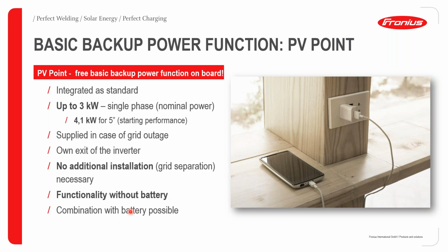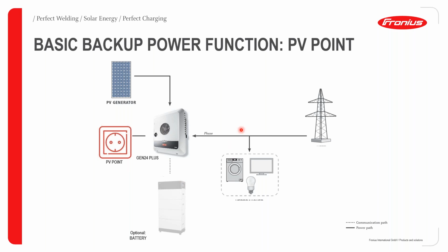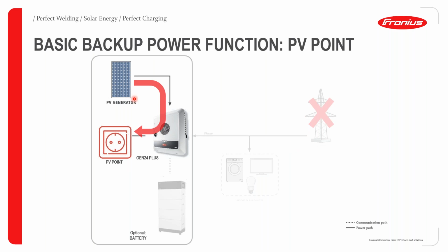So the combination is also possible with a battery system. If you have a battery system integrated, this is how a normal setup would look. You have a Gen 24 inverter connected to a PV array, and then you could have a battery storage or not. In case there is a grid failure, the Gen 24 takes this maximum of 3 kilowatts directly from the PV system and is feeding all the loads that are connected to the PV point.